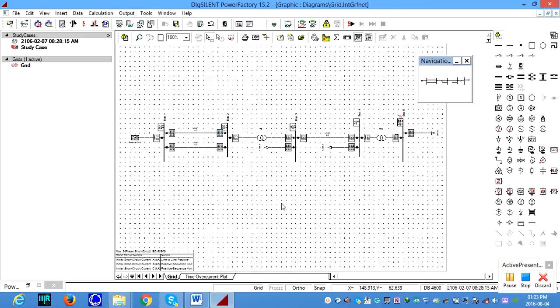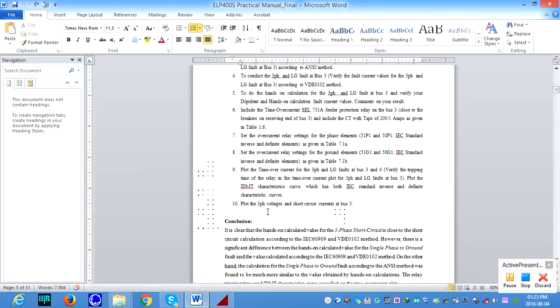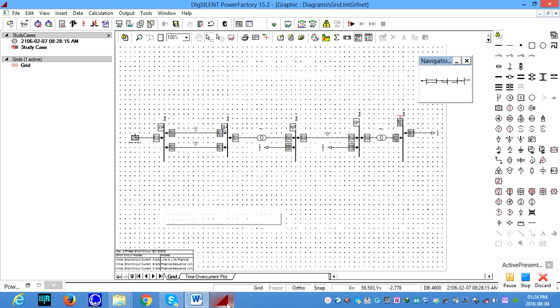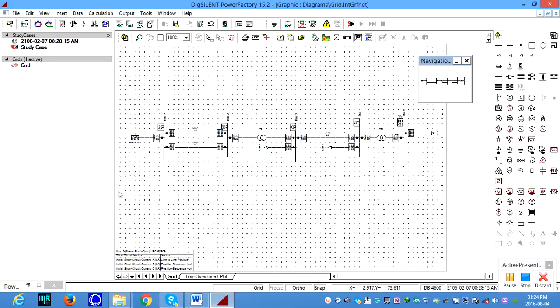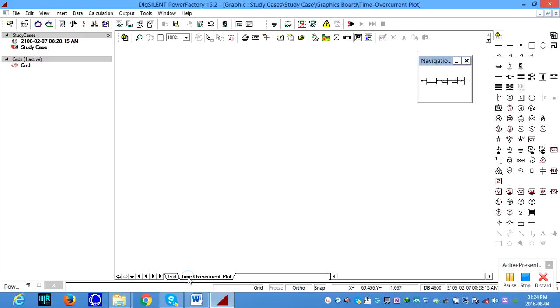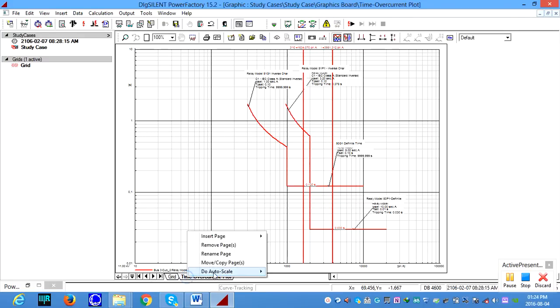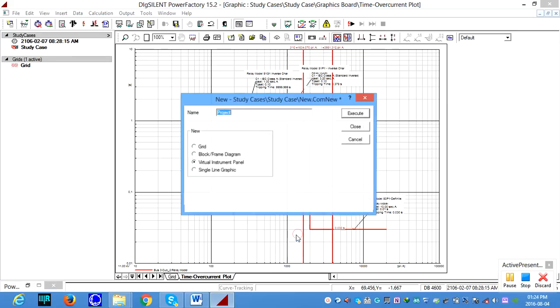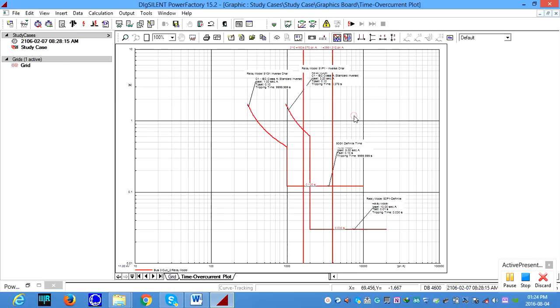The last thing, if you look at your manual, the last point, we need to plot the 3-phase voltage and the short circuit current at bus 3. So there is a separate procedure in order to create a plot in DIgSILENT. So in the next few minutes, I will try to explore how to plot the voltage and the current waveforms in the DIgSILENT environment. To do that, first you need to select any one of these things. Then you need to create a new page. From that, you can see either you need a grid or virtual instrument or single line graphic. The first thing we need is to create a virtual panel.